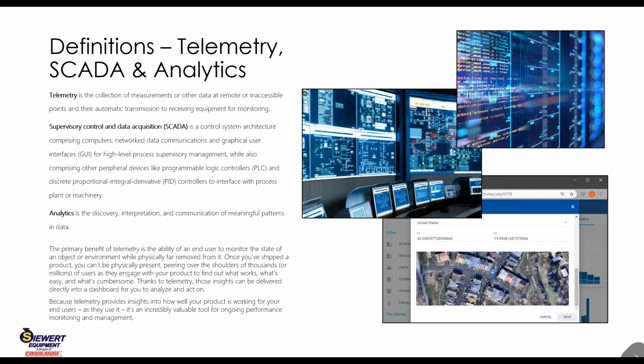The next step above telemetry is SCADA, supervisory control and data acquisition - a pretty fancy name, abbreviation is a lot easier. It's more than just equipment inside of another piece of equipment, be it PLCs or controllers inside of a panel. It's more than just solenoids or things that are monitoring door position, valve position, temperature, humidity, pressure. There's a ton of different things that SCADA is capable of monitoring. It really depends on the amount of signals you have access to, be it the analogs, the digitals, the inputs and the outputs. I've seen plants across the country using SCADA for so much more than what I expected them as water or wastewater entities to be using them for.